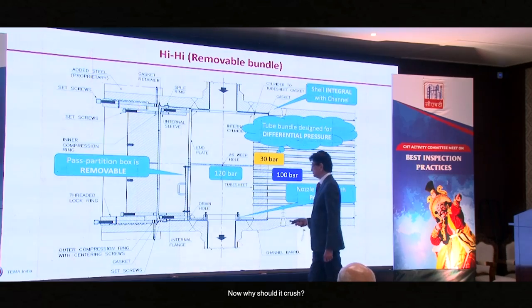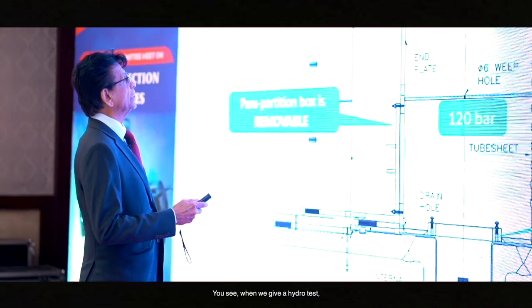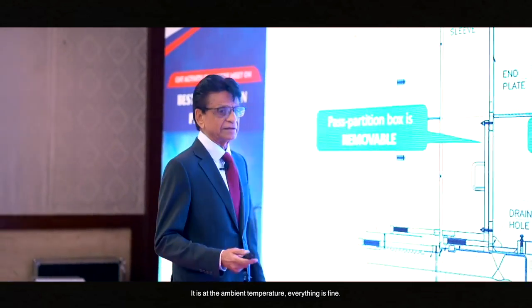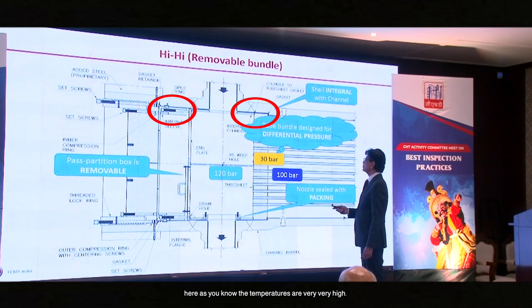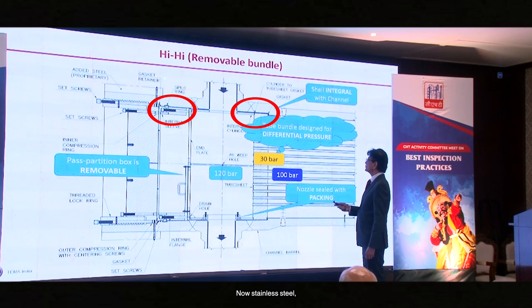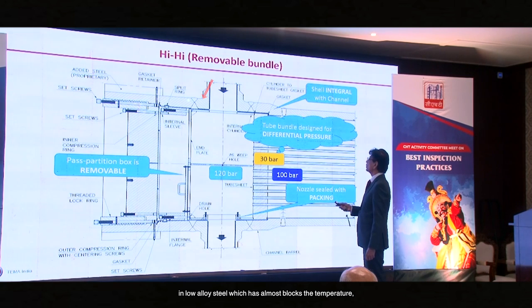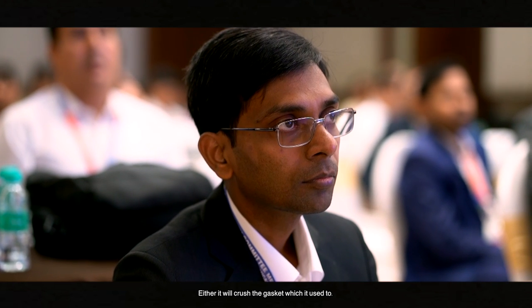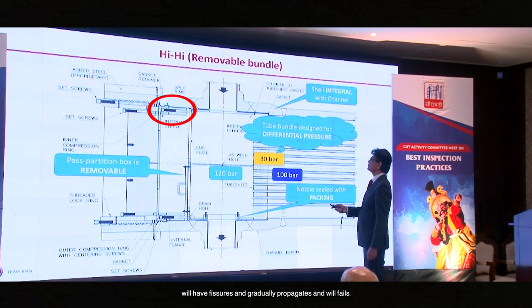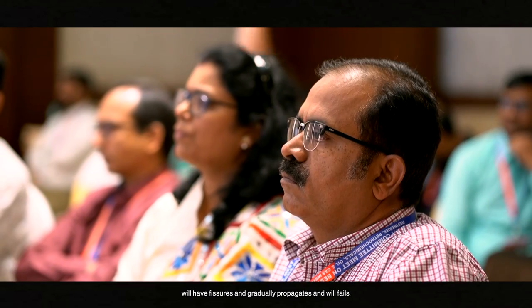Why should it crush? That is a big question. When you are giving the hydro test it is at ambient temperature — everything is fine. But in process, the temperatures are very very high. Stainless steel has a much larger coefficient of thermal expansion than low alloy steel, which is almost unaffected by temperature. So this expands — where is the load going to go? Either it will crush the gasket as it used to, or this notch over here will develop fissures and they will gradually propagate and it will fail.